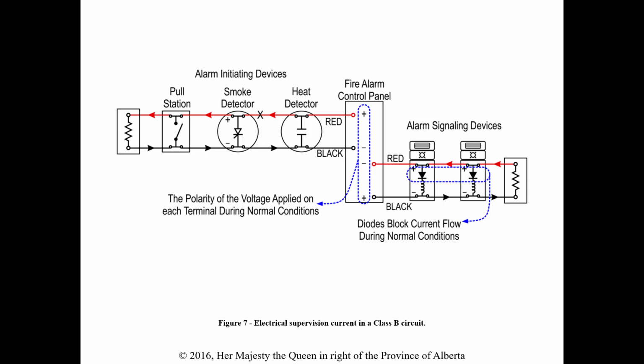Signaling device would be your warning, so that would be your beacons, your strobes, your horns. So here's all the signaling section, and this would be the initiating portion of it. So these are going to tell us we have an issue. Then the control panel is going to switch the polarity on the signaling devices, and then it's going to signal through there.